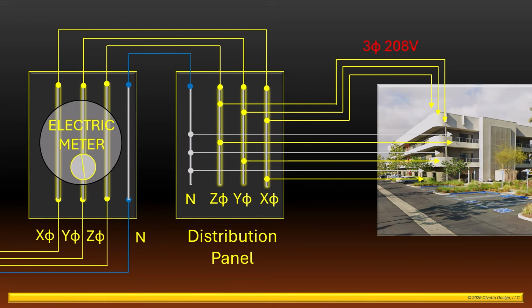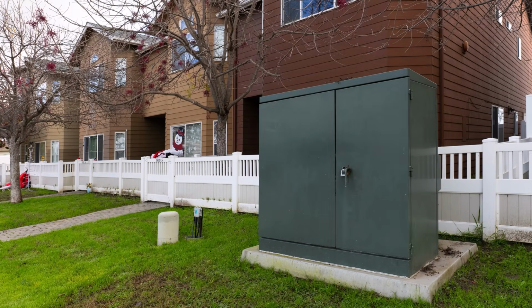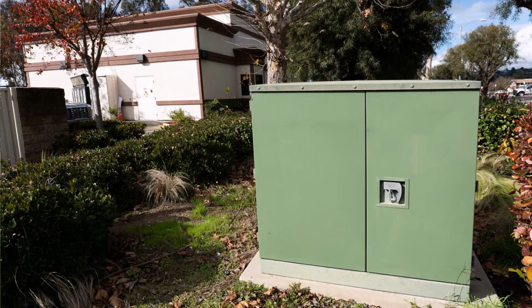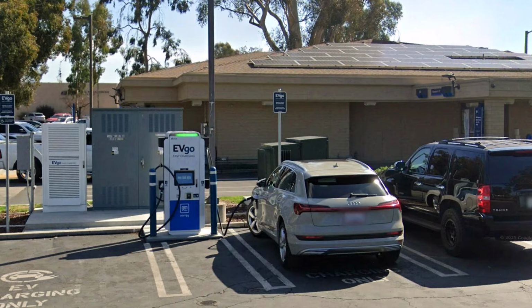The ability to evenly utilize all three windings in the transformer to provide a lot of single-phase 120-volt power is the advantage that this type of transformer bank has when compared to the delta-connected bank we looked at in the previous video. For the same reason, the pad-mounted version of this transformer is also used a lot to provide power to apartment buildings, fast food restaurants, and has recently become very popular for electric vehicle charging stations.